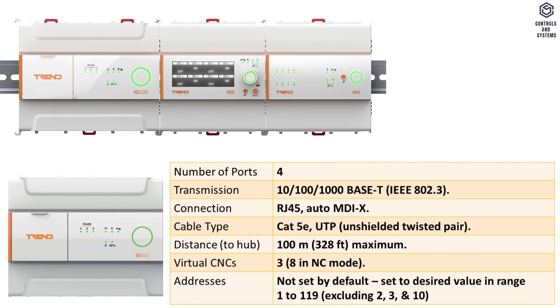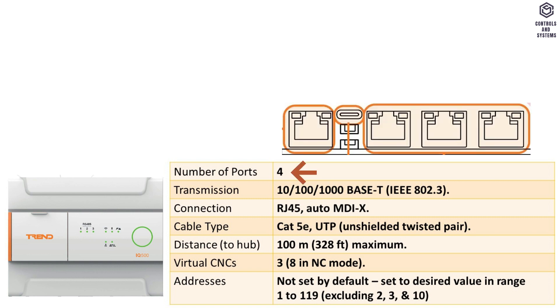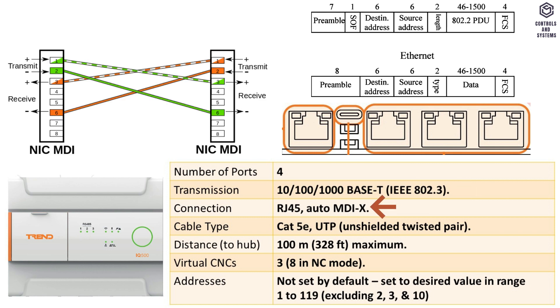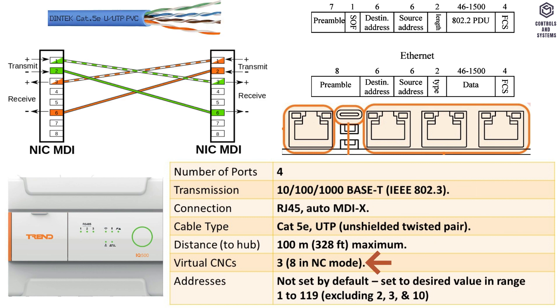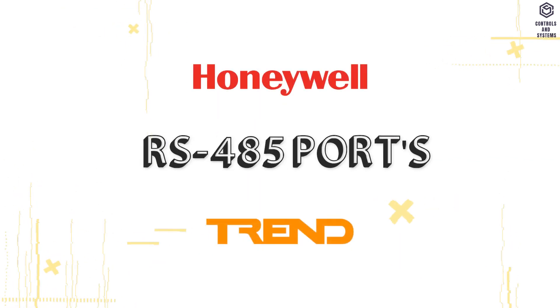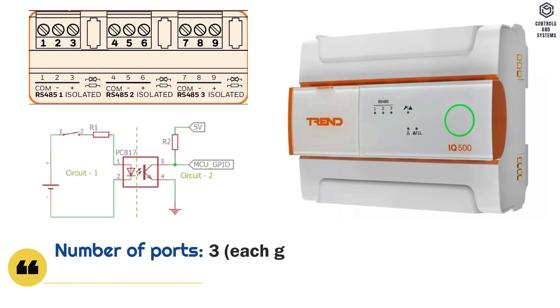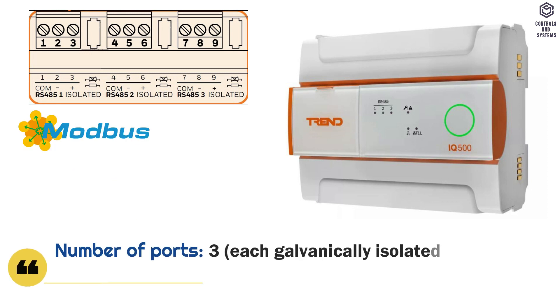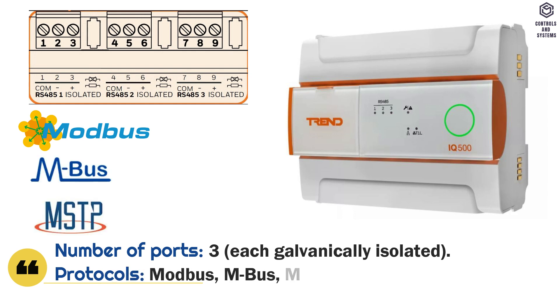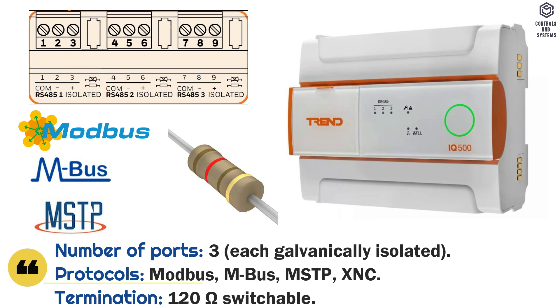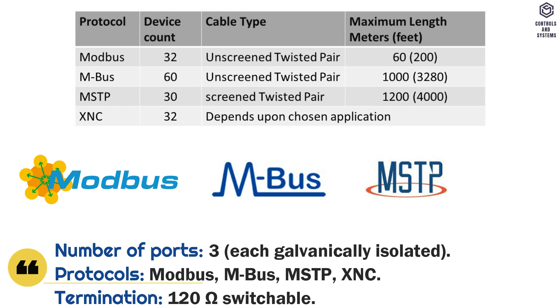Ethernet network: this table indicates the specifications and ranges of number of ports, transmission, connection, cable type, distance, virtual CNCs, and addresses. RS-485 ports: number of ports is 3, each galvanically isolated. Protocols are Modbus, MBus, MSTP, and XNC. Termination is 120 ohms switchable. This table indicates the specifications of protocols, device count, cable types, and maximum length.